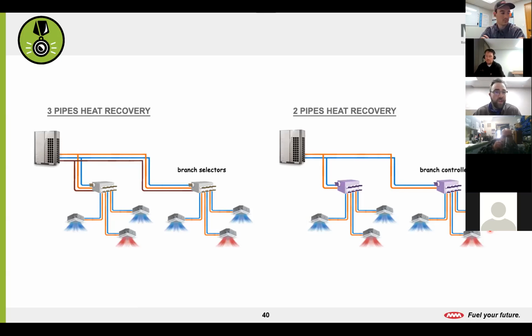As far as the operation, all VRF is the same process. The difference between the 2-pipe and the 3-pipe is where those processes happen. So with the 3-pipe system, I know we were talking about our high pressure gas or our hot gas. We have our medium temperature liquid, and then we have our low pressure gas. On a 3-pipe system, all of that is taken care of and supplied by our outdoor unit. On a 2-pipe system, our hot gas and our low pressure gas is handled by our outdoor unit, and then our medium temperature liquid is actually handled within our branch controller here.